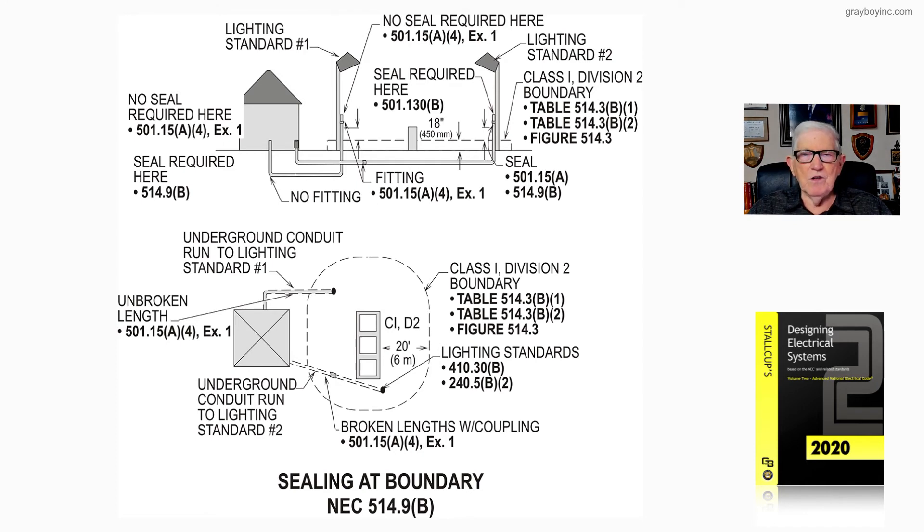That's what this illustration is all about — it illustrates when you run a conduit system underneath or into the boundary area where a lighting standard may be installed, you might have to seal. But if you don't have a coupling and can run unbroken lengths, you would not have to seal because you're not considered to be entering that boundary area.